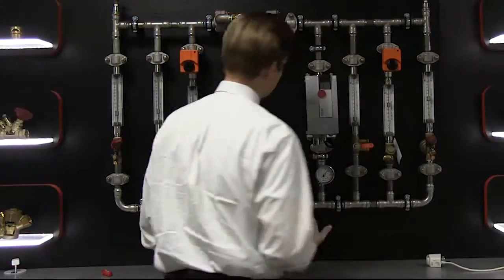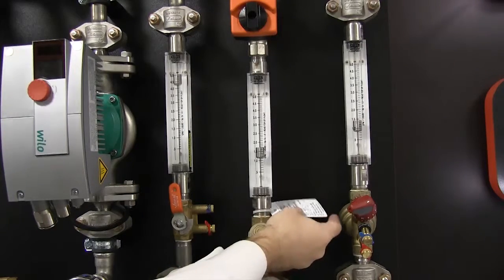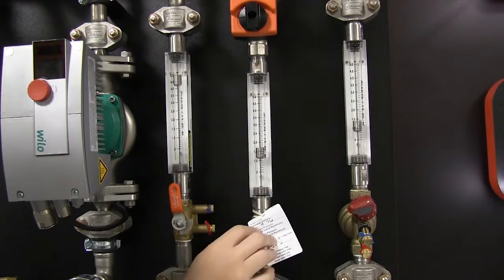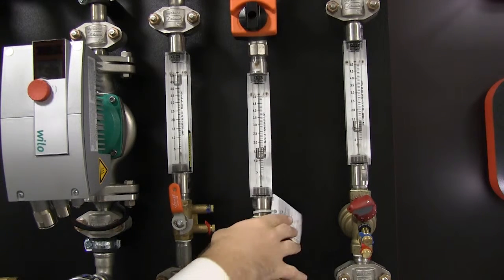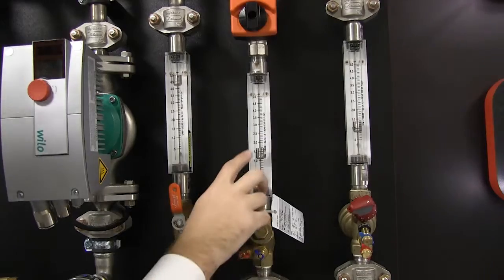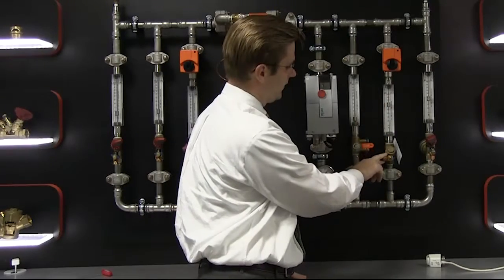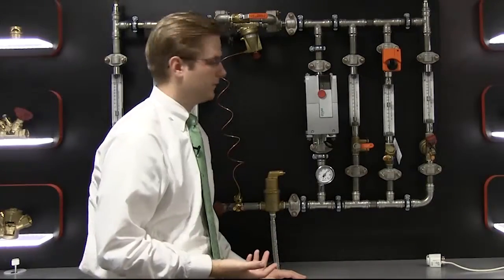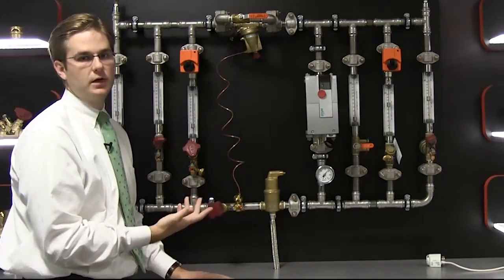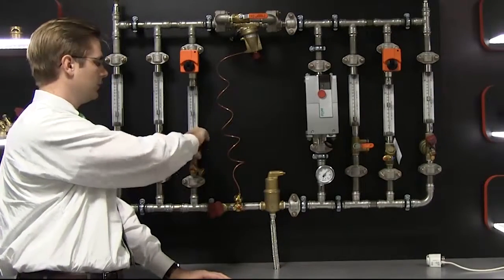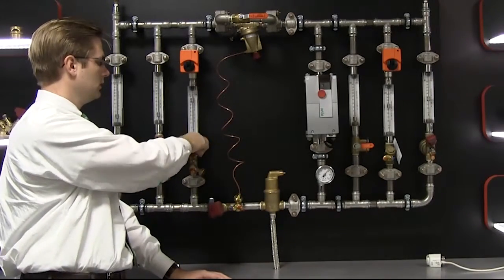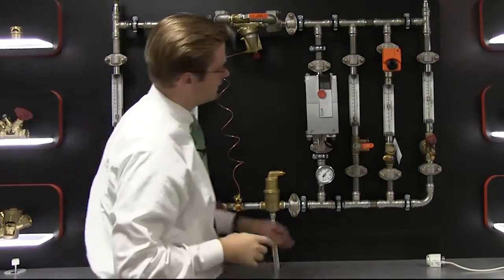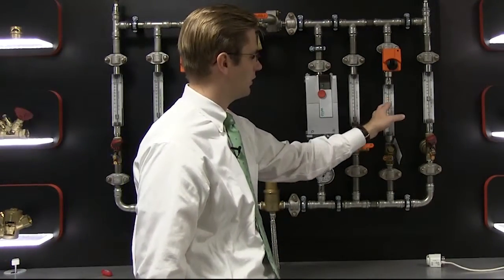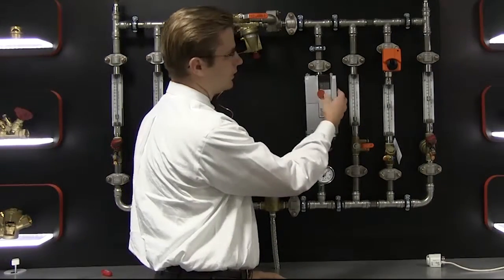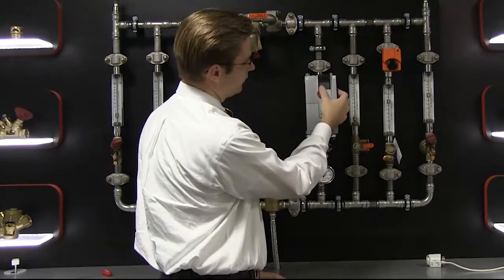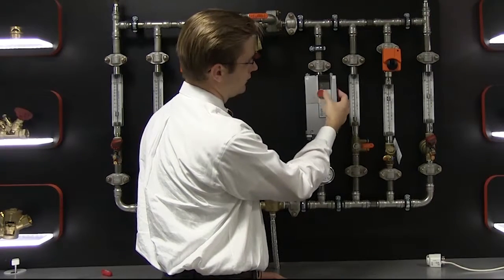One other way to balance proportionally is with an automatic balancing valve. Now this valve comes preset to 4 3/4 GPM, so it's going to maintain 4 3/4 GPM at all times. You'll notice, though, that I do need more pump head with an automatic balancing valve, in this case 2 PSI. With a manual valve, I need 1 foot of pressure drop. So you can see that with this valve full open, I have well over 5 GPM, but I still need more pump head in order to get 4 3/4 GPM at the automatic valve. Once I have enough pressure, the valve will maintain a constant flow rate.